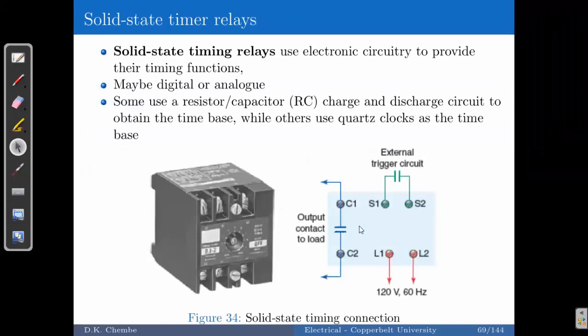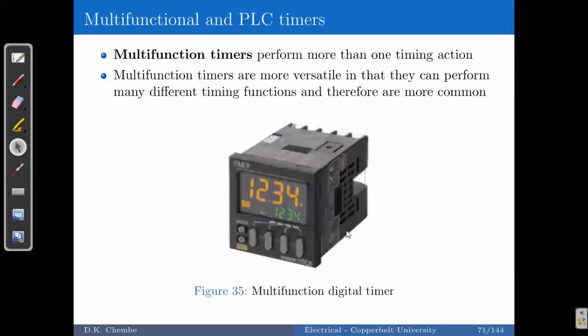The time contacts can be applied if you desire an operation requiring off-delay — you can set it in that way and use the solid state timer accordingly. Multifunction timers are mostly digital timers that can have more than one timing sequence, with a number of contacts performing various timing sequences. One may bring a unit or instrument on and off, and another operation may be cyclic — meaning repetitive — bringing an operation on and off at particular preset times.